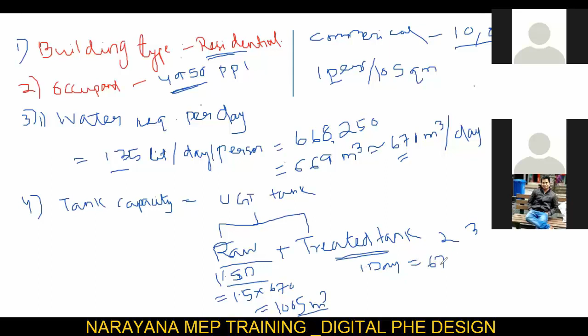Write down the capacity. This is for 1 day. Here for raw water, how much do you have to keep? 1.5 day storage. Multiply 1.5 into 670. How much are you getting? 1005. Next is the treated tank: you have to give storage of 1 day. Combined, raw water and treated, you have to give minimum 2 days, up to 3 days. Generally the practice is 2.5 day storage.